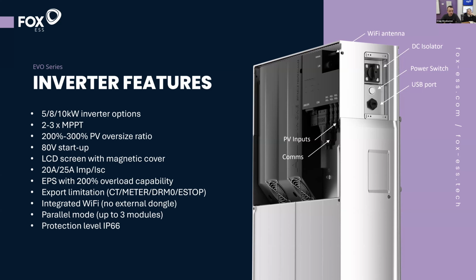It has a low start voltage at 80 volts. It will output at 80 volts, it doesn't need to hit a higher voltage and then work down to 80. So a 3-panel array is fine. We don't recommend 2 panels, even though your VOC might slightly be above the 80 volts - you've got the issue of voltage falling under load and things like that. So 3 panels is the recommended minimum.